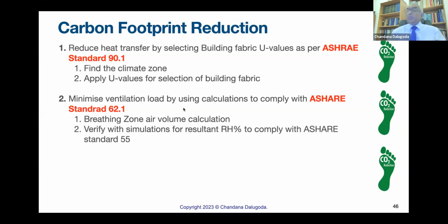to a building, because the buildings are now energy tight. And obviously the buildings are very thermally tight too. So infiltration is reduced. So we need outdoor air to dilute carbon dioxide in the building, dilute odors, dilute volatile organic compounds inside the building. When we bring outdoor air into a building, that consumes power.